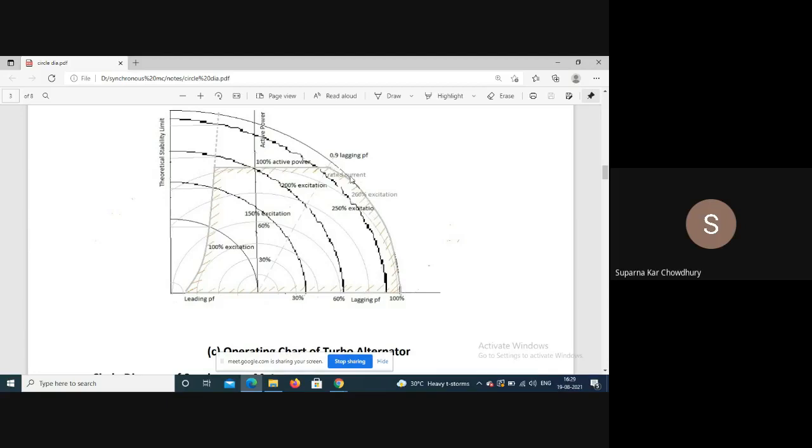The machine also has a rated excitation, since the excitation system must be designed accordingly. For example, if designed for 250% excitation, this is the corresponding excitation circle. The rated current circle cuts the excitation circle at a point. Beyond this point, drawing rated current would require exceeding the excitation, so output becomes dictated by the excitation circle.